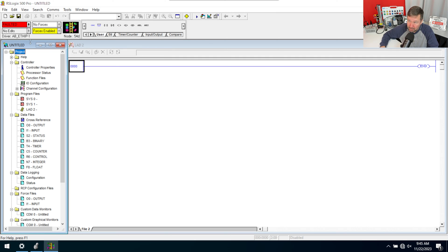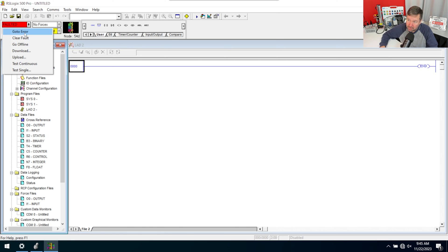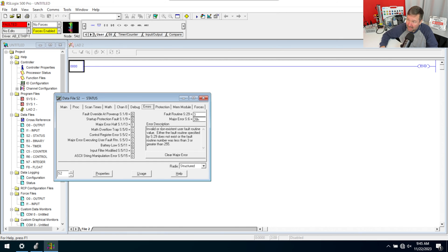I've replicated your exact error here. We have a fault, so we're going to go to error. And we see: "Invalid or non-existent fault routine value. Either the fault routine specified by S29 does not exist, or the fault routine was less than three or greater than 255."